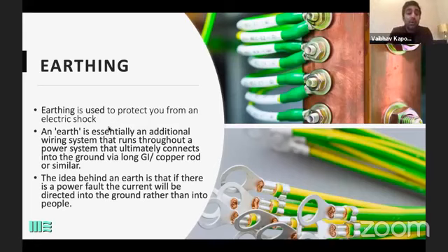That system will automatically trip. If it will not trip, you will become in between, and then from the wire, it will go inside the ground. So the neutral has to be earthed every time you're doing any genset work, especially. In the case of house power, you don't need to worry about the neutral earth because it has already been earthed from the grid. So the only earthing you need to do is the body earth.